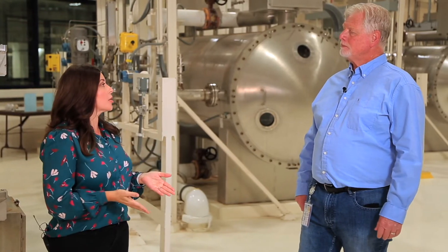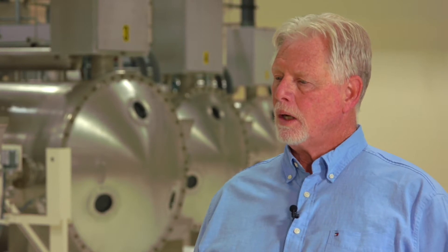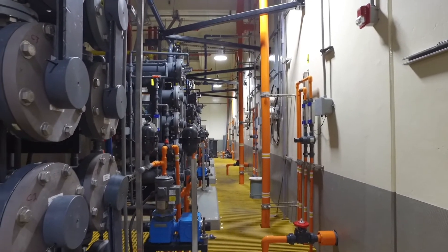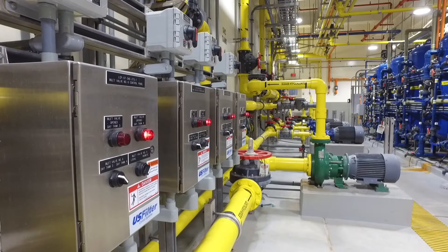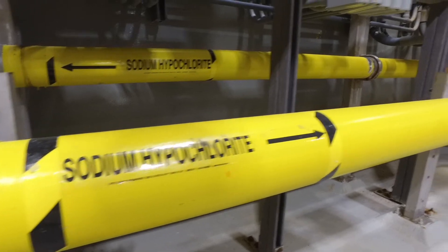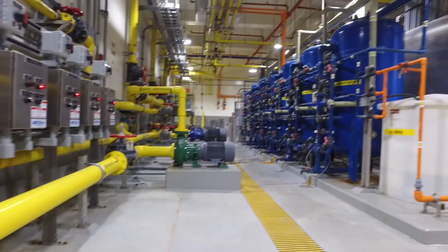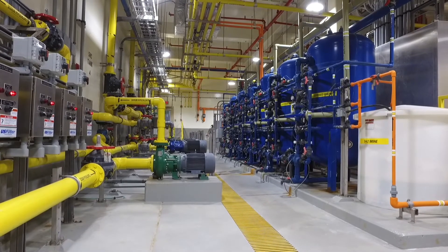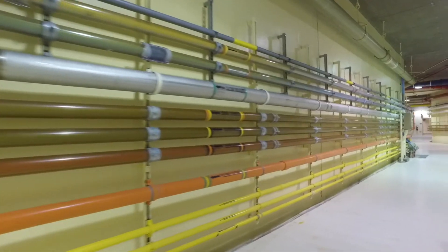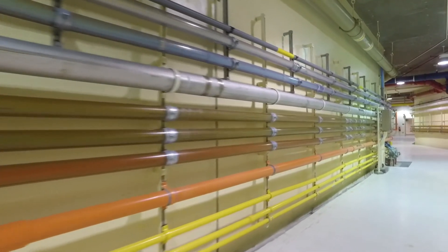We also produce chlorination here at River Mountains. This is a pretty unique plant in that we actually manufacture our own chlorine bleach. We take salt delivered in 40-ton trailers, add electricity and water, and that combination gives us 0.8% bleach, which we then use to disinfect the water. We add it right after the ozonation process so it goes through filtration, then add a little extra at the end so there's a residual effect as it goes out into the distribution system.